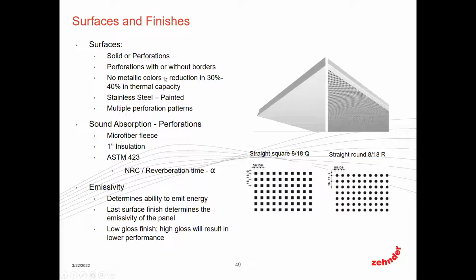Different types of color, or excuse me, different colors. A couple notes: just stay away from metallic colors. Metallic paint has a flake in it, which actually affects the emissivity, which is what drives the actual performance of the panel. So you want to stay away from that because that will reduce your thermal capacity. And then also stainless steel, it's very shiny, has a low emissivity. If you do need to do a stainless steel, you want to make sure that's a painted stainless steel, so you change that final surface finish.